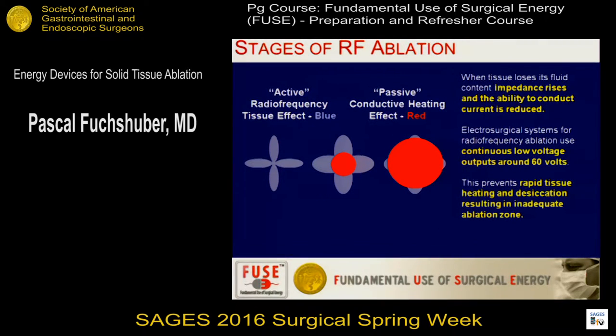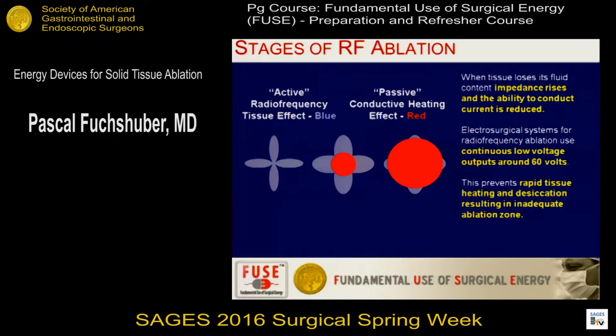It's a combination of tissue effects. We have the direct ionic back-and-forth kinetic effect, but most of what we see with radiofrequency ablation is actually a thermal effect — a passive conduction of energy. We want to maximize the time in which tissue still contains fluid, minimizing the time it takes for impedance to rise. Electrosurgical systems for RFA therefore use very low continuous voltage, around 60 volts, which prevents rapid tissue heating, desiccation, and inadequate ablation zones.